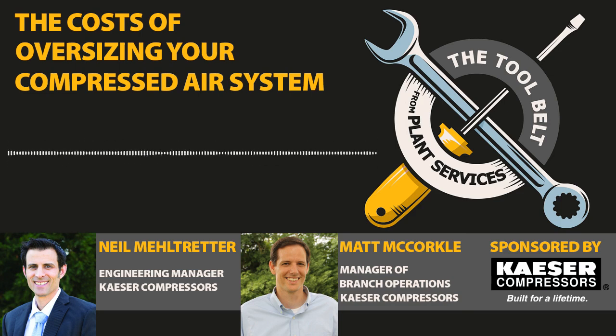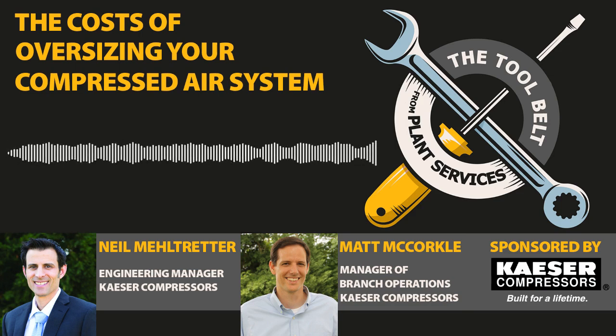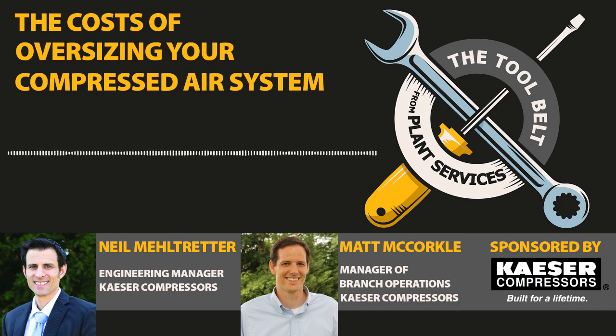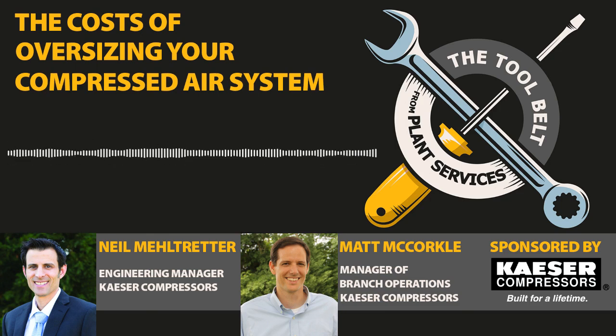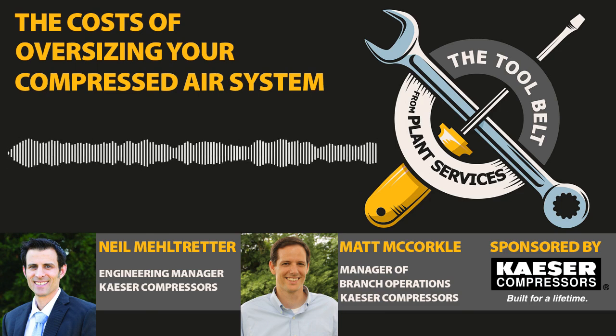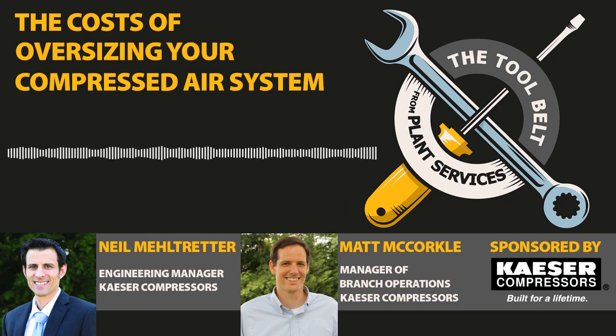And then the third one, a little bit higher cost. A lot of times plants have different loads based on the shift. You might have a very low third shift or weekend shift, and shifts 1 and 2 you're at 70, 80% capacity, but on the weekends you're at like 20% capacity. In those cases, you conduct an air study, and you could get a smaller unit to run those off-peak times. Those are the three most common.